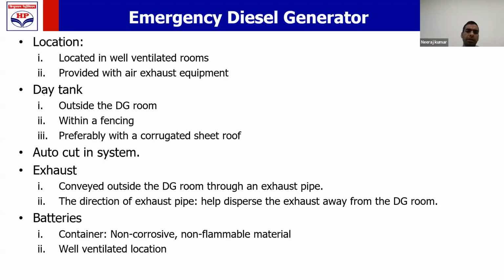Now, how and where should the day tank be? The day tank should not be inside the DG room. The day tank shall be outside the DG room, and this day tank shall also be provided with fencing. Preferably, not a compulsory requirement, the day tank will be provided with a corrugated sheet roof. Why? So as to protect it from the rain and sunlight. So your day tank shall be outside the DG room, will have fencing, and if possible should also have a corrugated sheet roof.